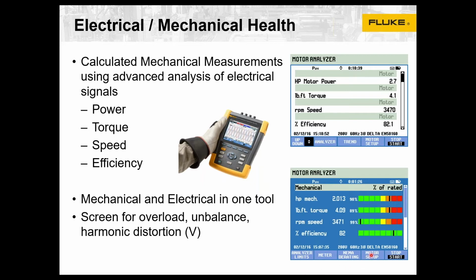Well, from a dashboard approach on the tool, you can see that if you are operating up in maybe a red condition, that might be an overloaded condition. That's going to shorten the life of your motor. So it'd be great to know if you are operating it in that condition. Some of the factors, overload, unbalance, harmonic distortion, those can all shorten the life of a motor, and having that power quality and motor analysis screening tool, if used proactively, can help identify potential issues that you can then take a deeper dive and find out why. Why are we operating in overload or an unbalanced condition?